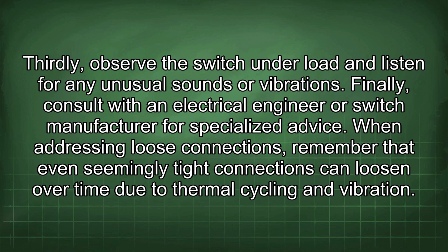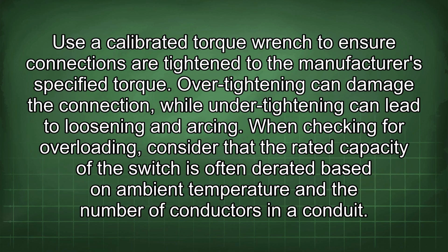When addressing loose connections, remember that even seemingly tight connections can loosen over time due to thermal cycling and vibration. Use a calibrated torque wrench to ensure connections are tightened to the manufacturer's specified torque. Over-tightening can damage the connection, while under-tightening can lead to loosening and arcing.